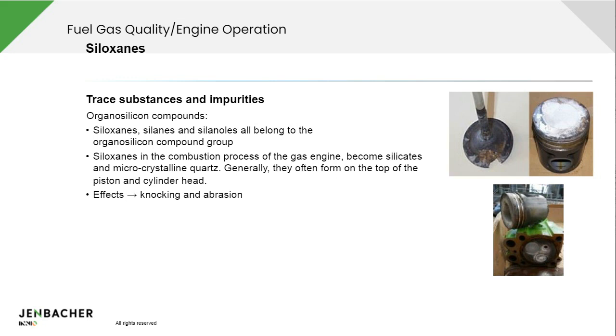So in essence, you have this sand-like substance in there, which is obviously the last thing you would like to have in an engine, as it will start pitting the valves. It will form these crusts on the pistons. It will coat pretty much every part of the combustion chamber, and will obviously affect the combustion. It will lead to knocking combustion, as the gas does not burn evenly anymore. It will lead to abrasion and ultimately failure of that cylinder, or potentially the whole engine if you have that issue on all the engines. And then you'll have to replace the cylinder heads, the pistons, valves. So rather costly.